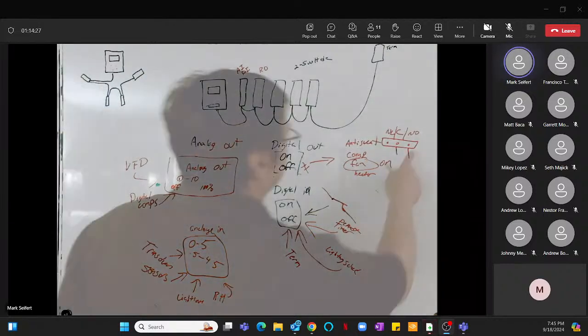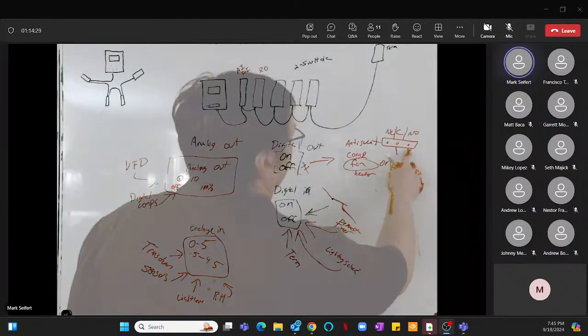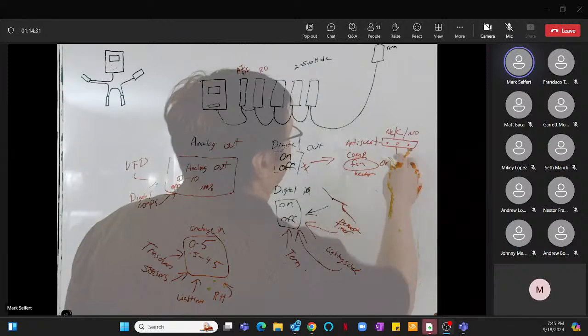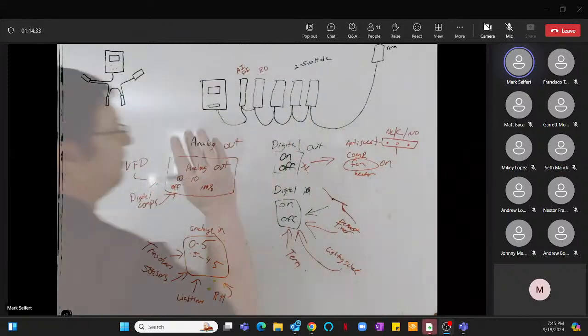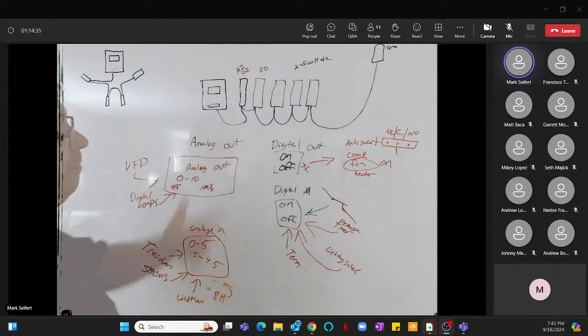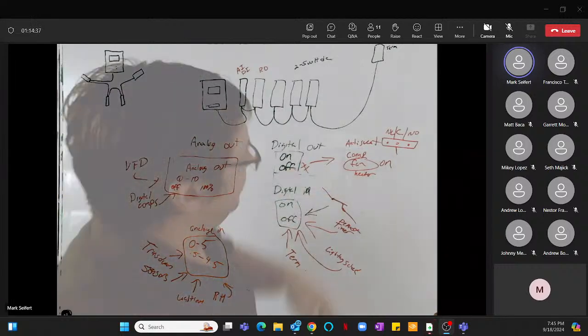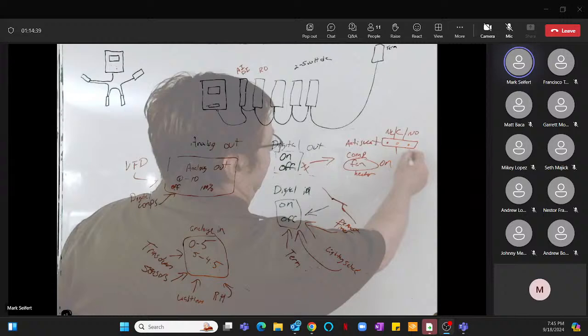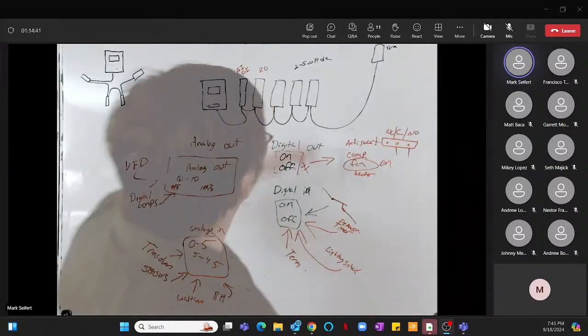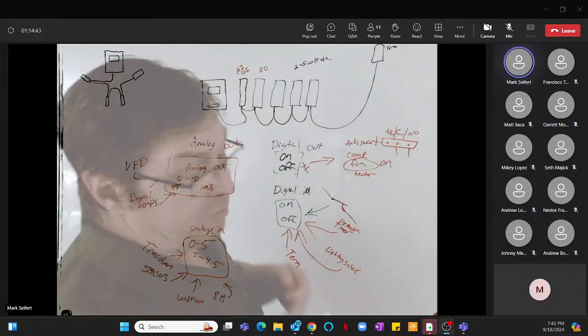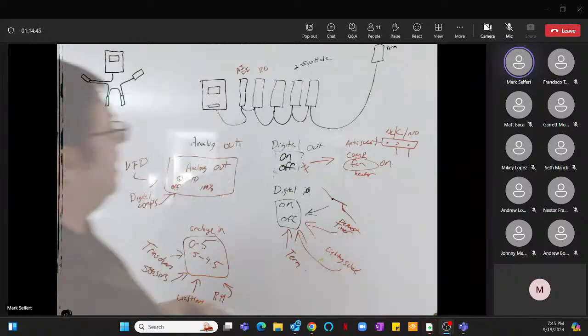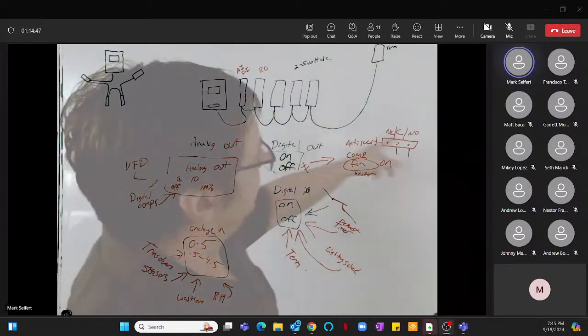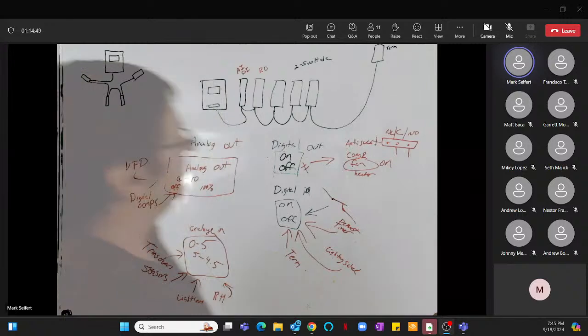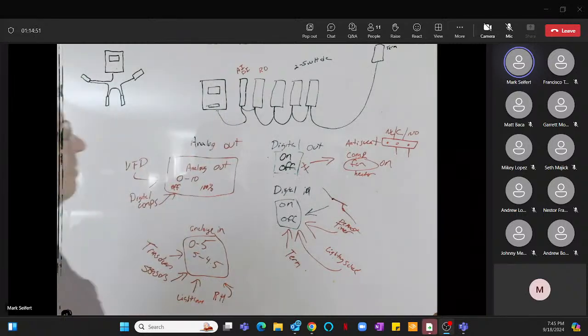And we do this, and I'm going to say that's almost always the rule, but we're going to call that always the rule right now, and I'll come back to where it's not always. But defrosts are always normally open, and we do that in case you lose power to these boards. It goes into what we call fail-safe, and it will fail compressors on, defrost off. We do not want these things failing into defrost. That's bad.